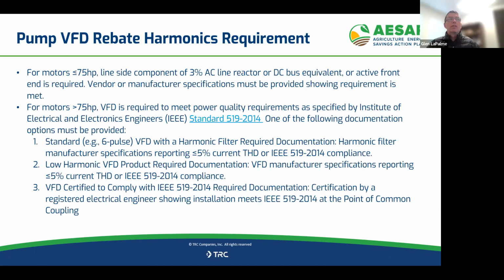No, but I think you just answered the question about VFD requirements. In that example, we talked about an active front end or a 3% AC line reactor or DC bus equivalent. That would be an example for a pump under 75 horsepower. On the question regarding the retirement of tier 1, tier 1 wasn't retired per se, but it allowed for modifications to a drive, by adding a filter or purchasing a low harmonic VFD, without complying with all requirements from the ITRC spec sheet.